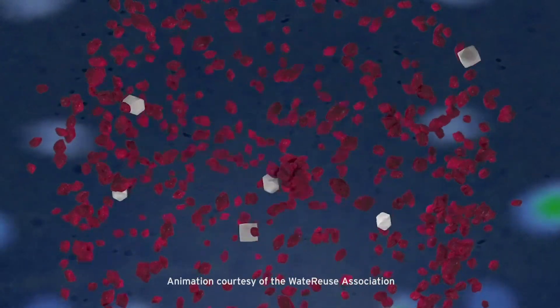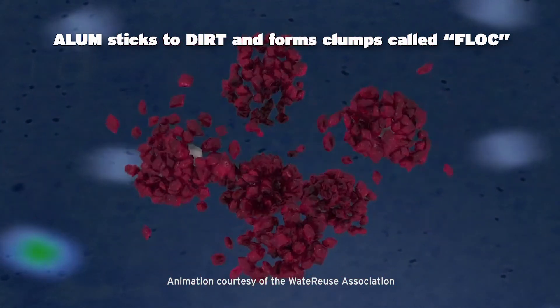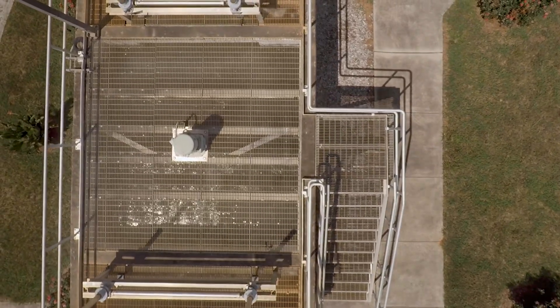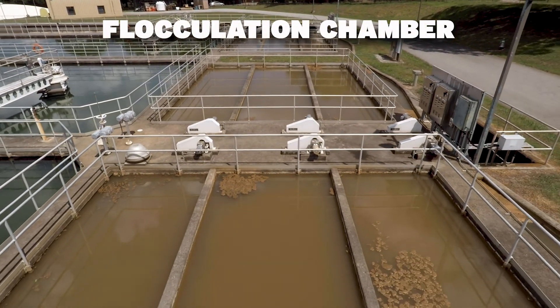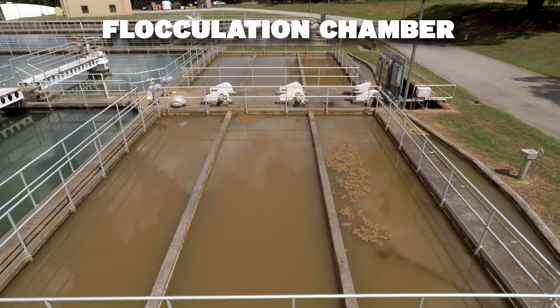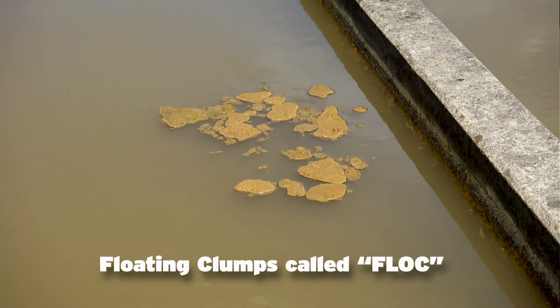For water treatment, alum is useful because alum sticks to dirt and dirt sticks to alum, forming this big clump — what we call floc. So let's get back to the water treatment process. After the raw water has been stirred up with our chemicals in the rapid mix chamber, the water is then directed into troughs and flows into the flocculation chamber. It's here that motorized mixers help the alum and powder-activated carbon evenly mix in the raw water, forcing the dirt particles to stick together, forming the floating clumps called floc.